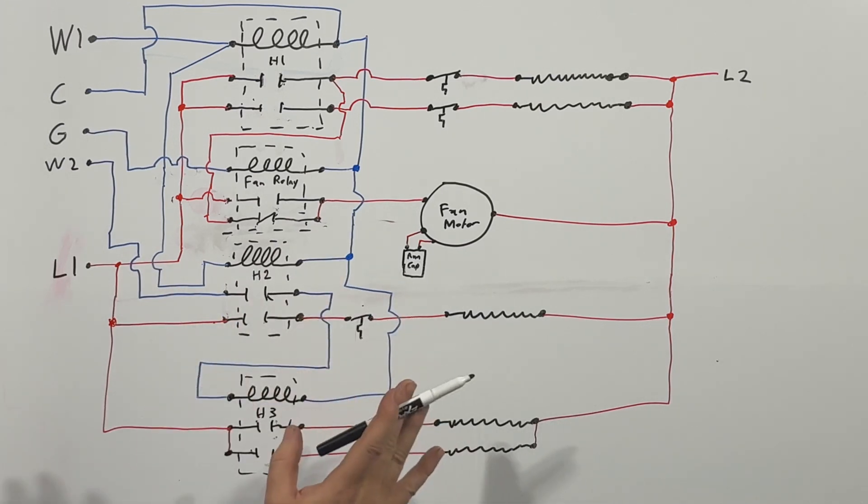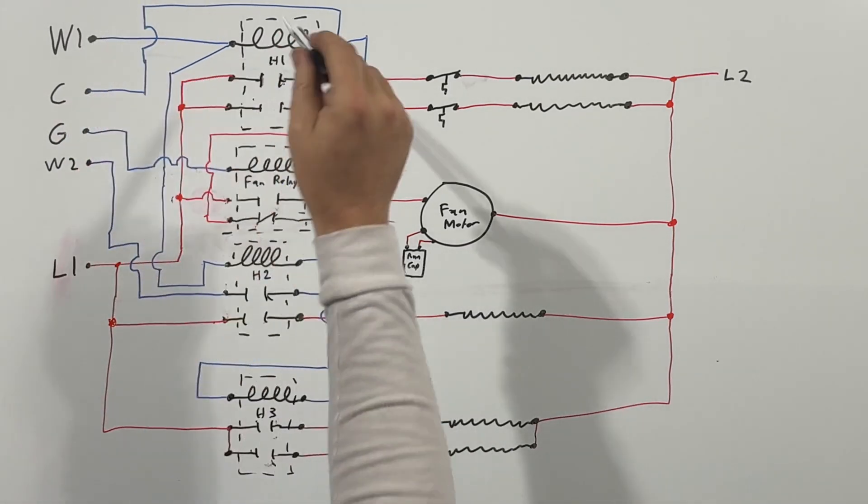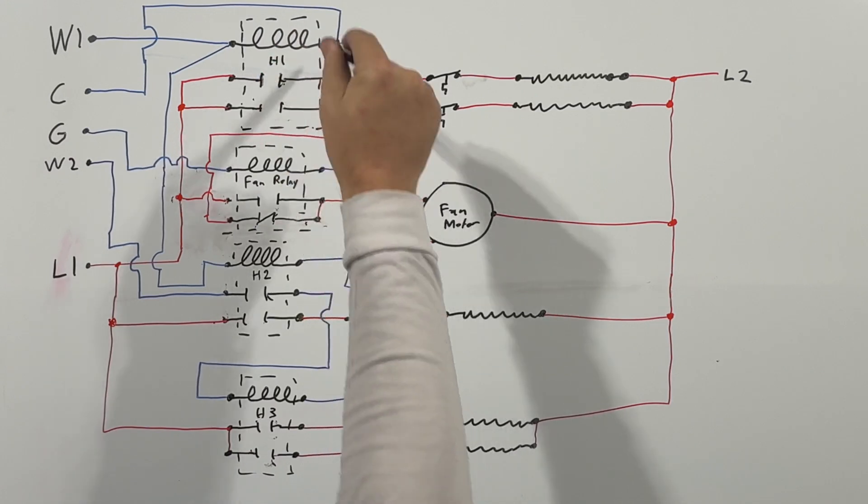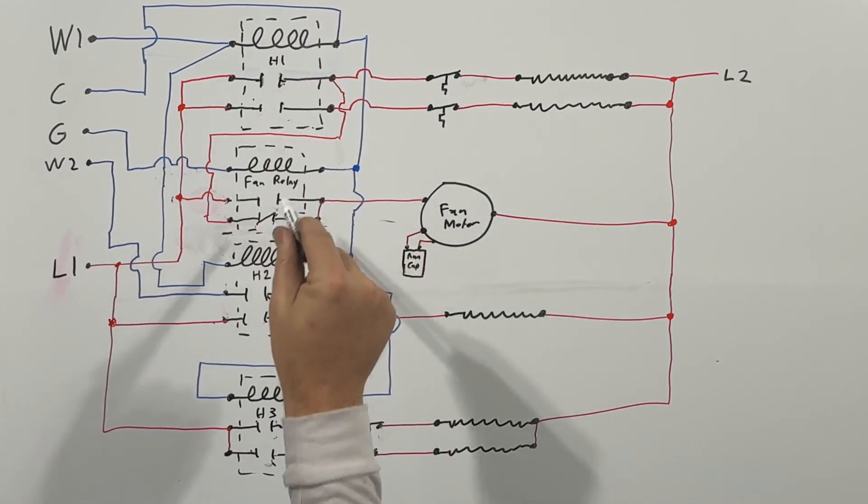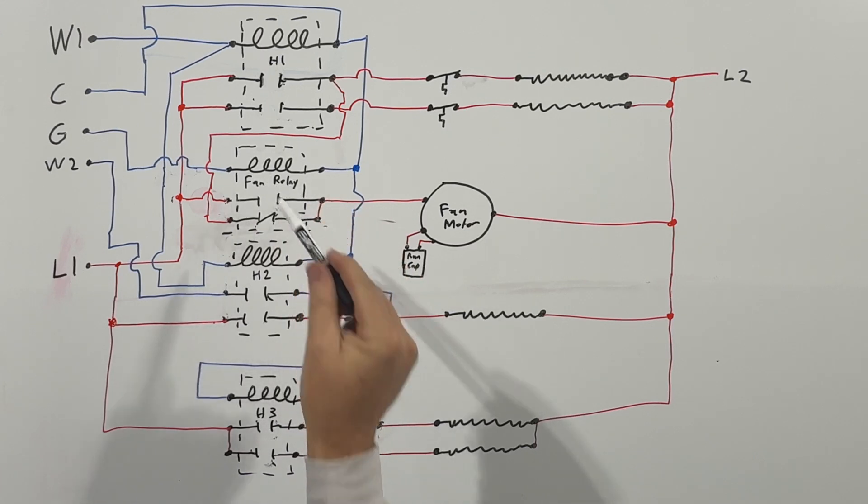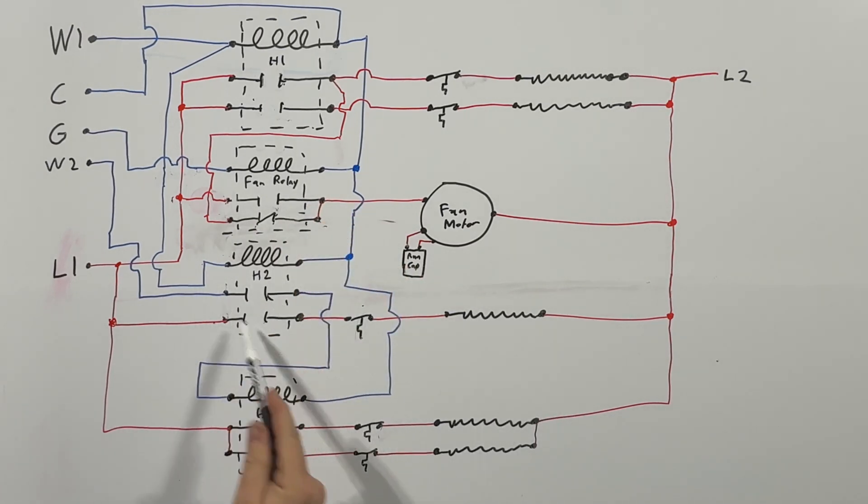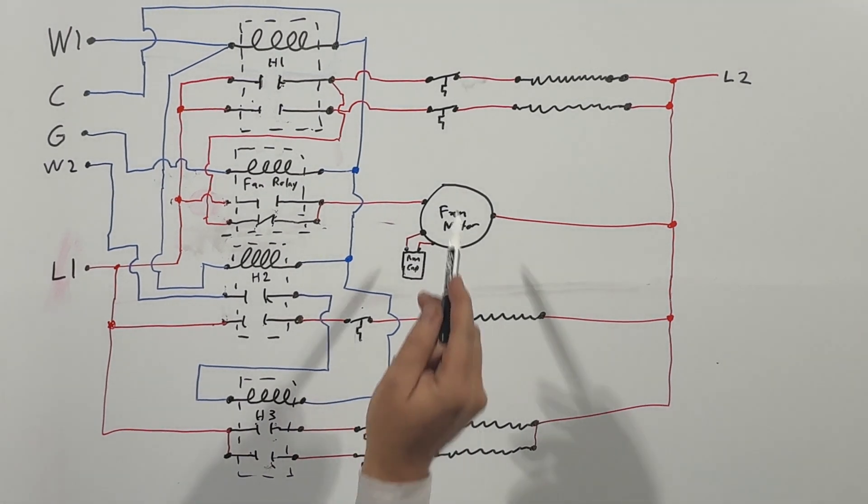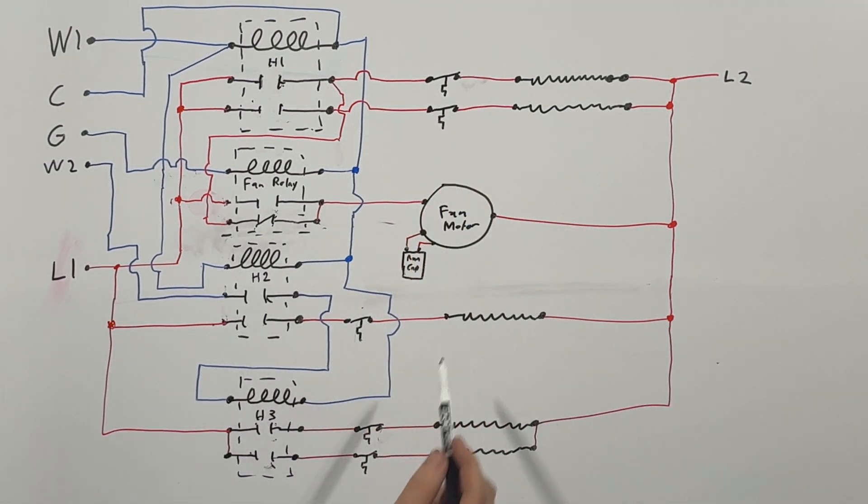So anyway, we have one relay here. This is a double stack sequencer here. We have a fan relay with a normally open contact and normally closed contact, and then we have another sequencer to stack right here and another sequencer down here. These are electric strips, blower motor, and these are our high limit switches because they're temperature switches.